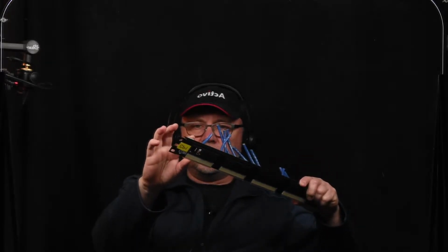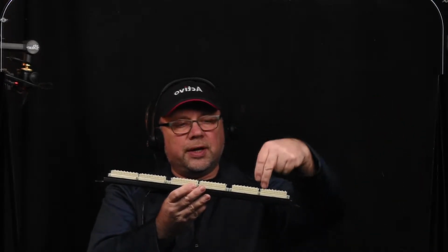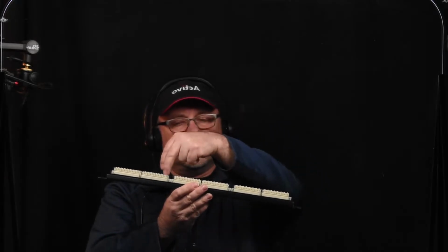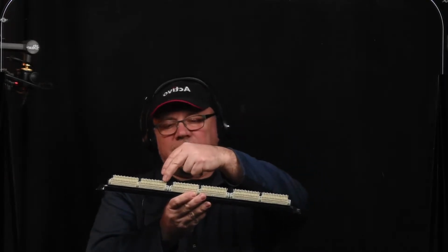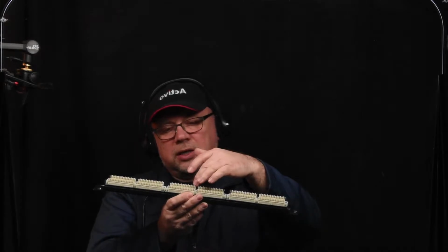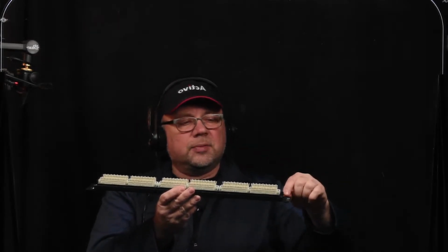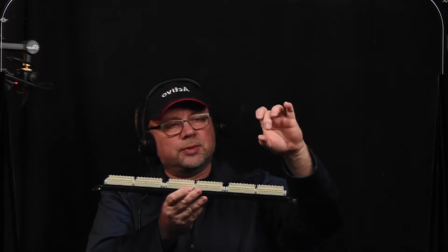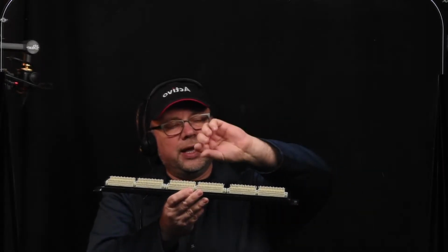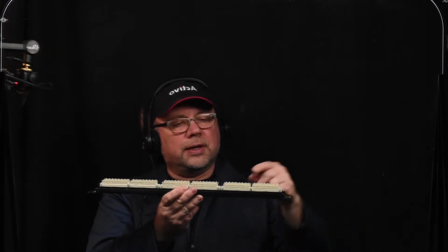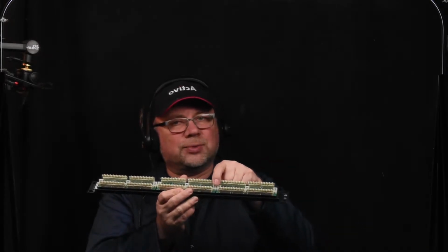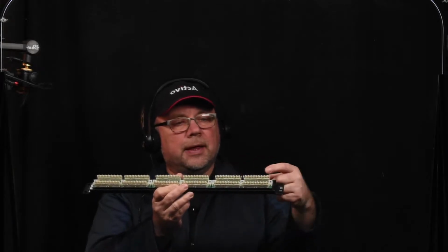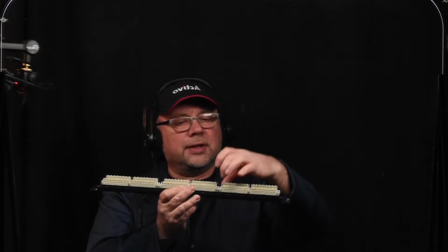So basically, the difference in termination is that with the loaded one, you're going to have to run the cables in a certain way and bring them to the IDC, insulation displacement connections, and terminate them. Sometimes you're going to have a support bar that goes on top that you can zip tie the cables to and mount them, or you can use those zip tie mounts here in order to fasten the cables.